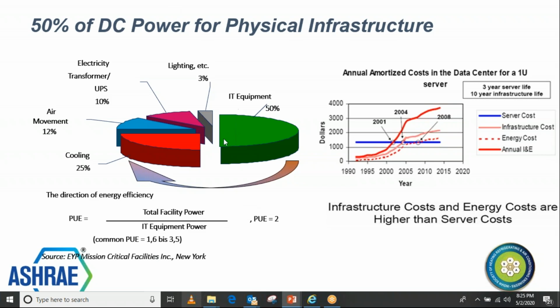Which means a PUE of 2 means 50%. Suppose you are giving 100 kilowatts of power to a small data center, and 50 kilowatts goes to the IT equipment while 50 is consumed by the other services which are supporting that data center. That is what is called a PUE of 2 here: 50 plus 50 is 100 together. So imagine that you are reducing this factor. Then this IT power will start going up and this will start reducing. The PUE factors are typically around 1.7 to 2, but all the new data centers designed in the last 2 to 3 years, especially the bigger data centers, have been designed around a PUE level of 1.4 to 1.6.